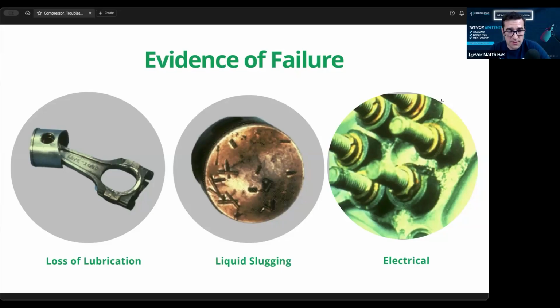You don't know the application. You don't know the refrigerant, but just by looking inside and inspecting it can tell you what actually happened to that compressor. Do you want to talk about that story a little bit when you're doing an inspection, and what's your process when you're doing a compressor inspection? Well, we look for broken parts most of the time. If it's been slugged, it's got broken parts. That the surfaces are good for lubrication. Valve reeds mainly, blown gaskets and all.